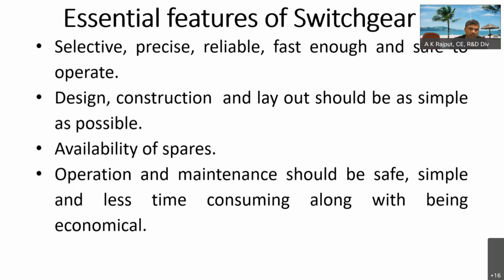Even prior to deploying in the field, they have to pass several types of tests. Those include the type test as well as the routine test at the factory. Design, construction and layout should be as simple as possible. This is very important for any type of machine or installation. Then availability of the spares has to be ensured. There may be chances that the product is going to become obsolete. It has been dumped to the utility at a very low price, but later on, the product has become obsolete and its spares are not available. So ultimately, it will be a very costly affair, and downtime will also be there.